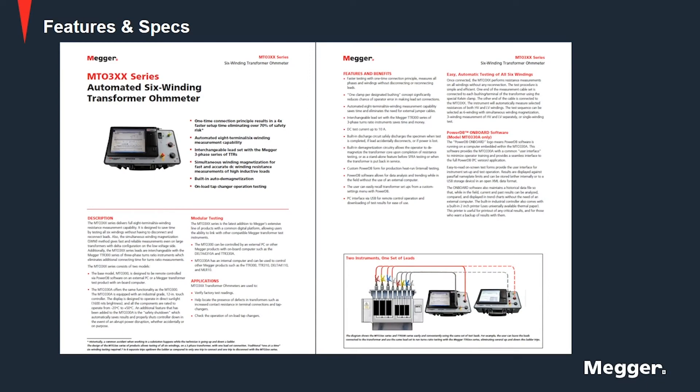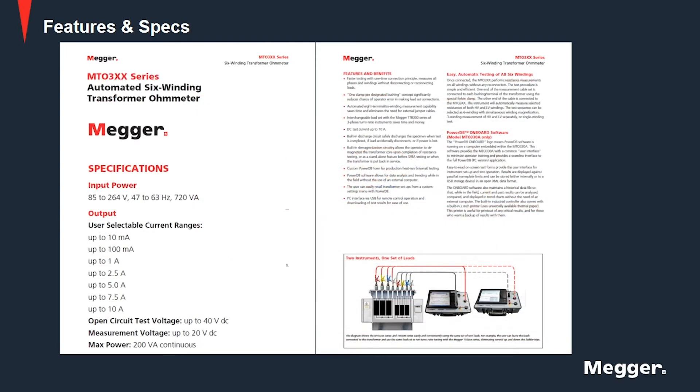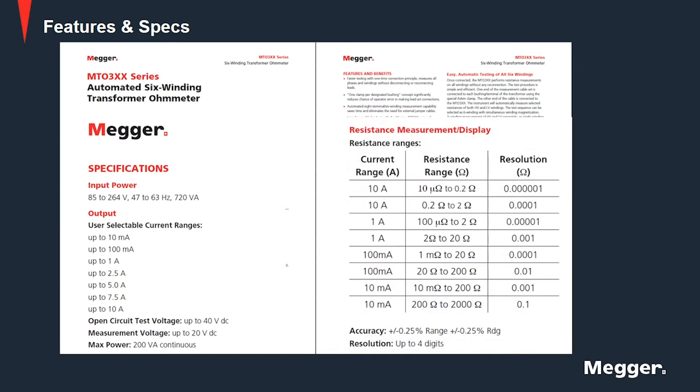The Megger transformer ohmmeter is a field portable instrument designed to measure the DC resistance of all types of magnetic windings. It can test rotating machine windings and perform low resistance measurements on connections, contacts and control circuits. It has user selectable current ranges from 10mA to 10A, and a resistance measurement range from 10 micro ohms to 2000 ohms.